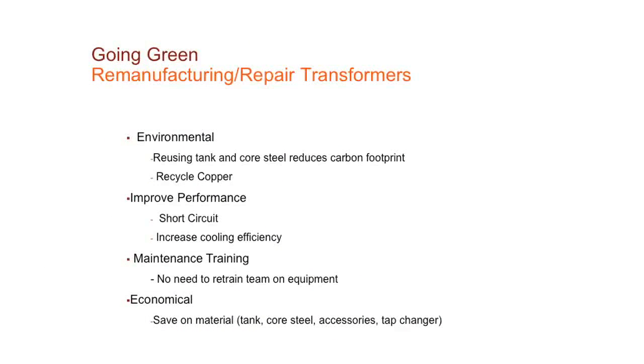Of course, it all depends on the design of the transformer. When you get to the larger transformers, these percentages will shift a little bit differently, as well as if you go into lower MVA transformers. But this is what we have found on a specific example. These can range, for instance, the conductor on a typical repair job, we count that as 23 to about 26%. So there is a range when you start looking at the percentage of cost for the material.